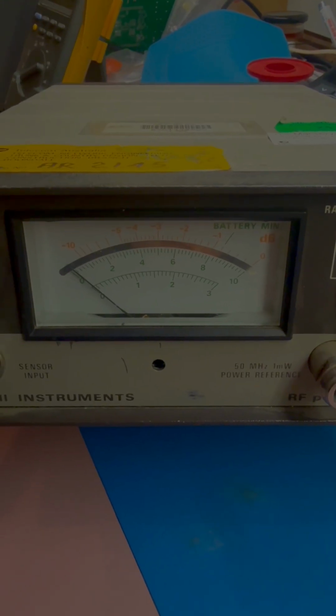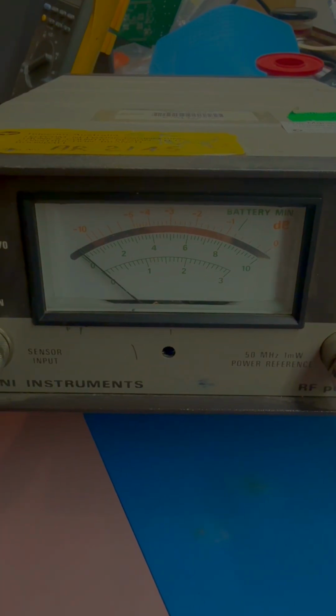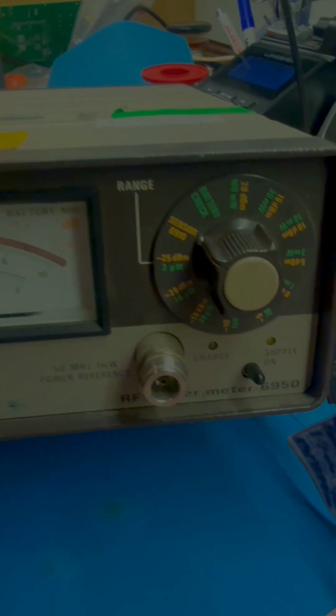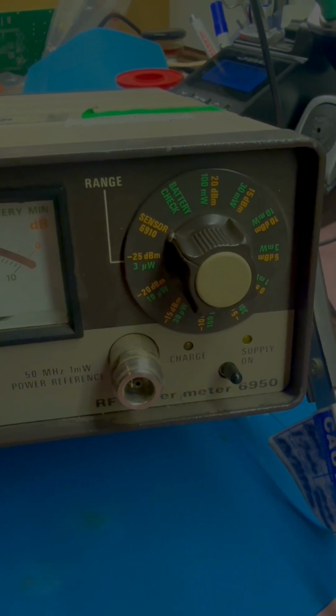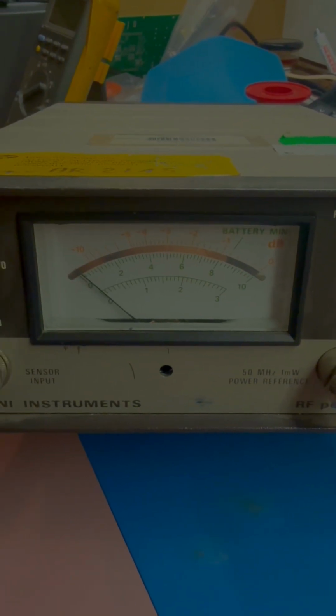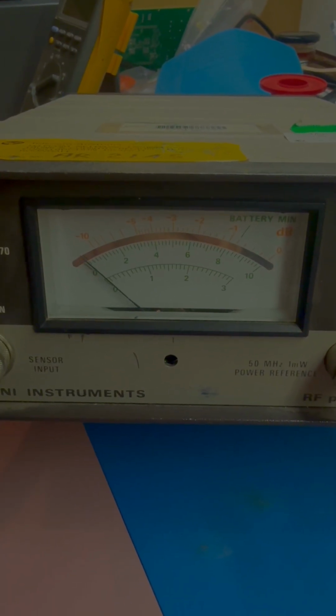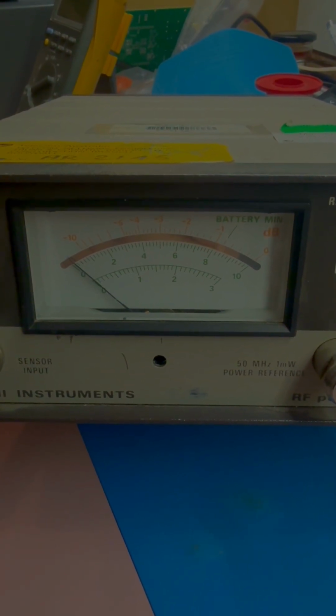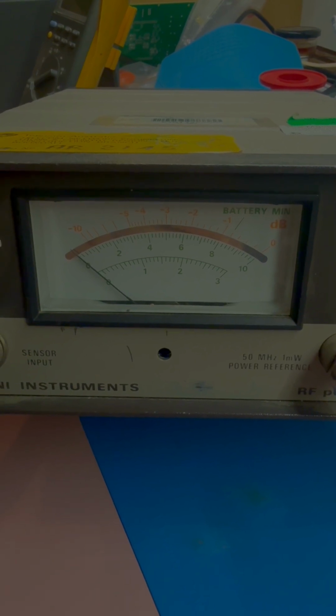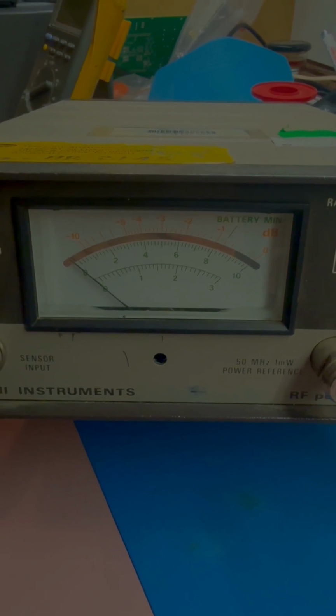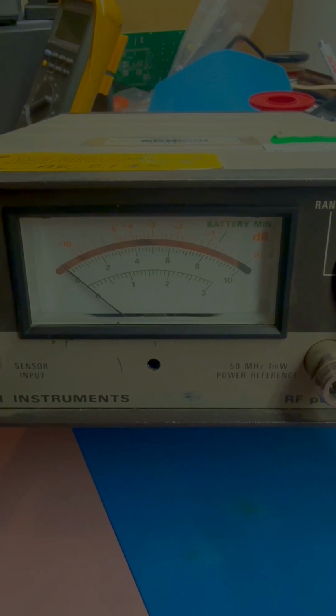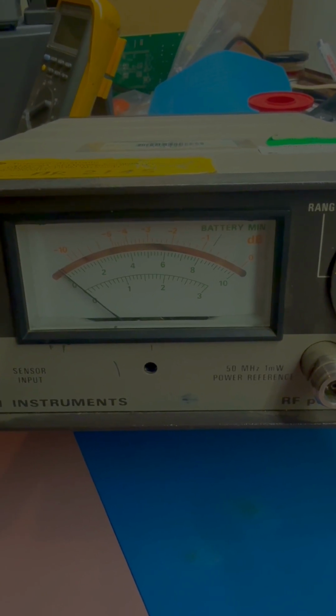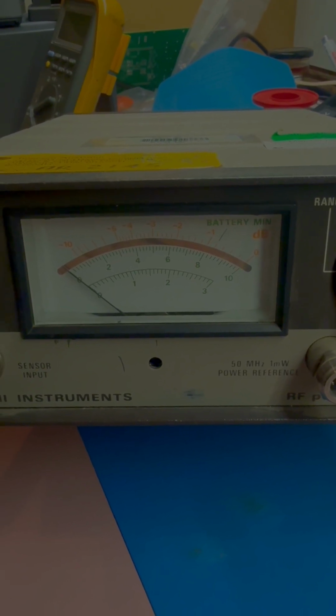So we finally got that sitting close enough to 0, and this is on the most sensitive range, which is the -25 dB range on this instrument. So that's the 0 calibration for the sensor. Now we'll go to the gain calibration. I'll put the phone down and connect the sensor.